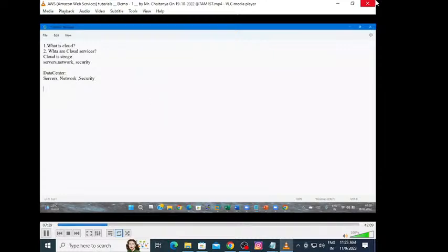Now, how can we select an area for a data center? If I want to install a data center, how can I select an area? The first thing you need to check is the power. If a company has 10 computers in a room, then definitely we need to have an AC. But in a very big data center where there are thousands of racks, and inside them thousands of servers, how much cooling will the servers require? And regarding that, how much power does a data center require? So we need to have high power availability, so that the data center gets power from two substations.